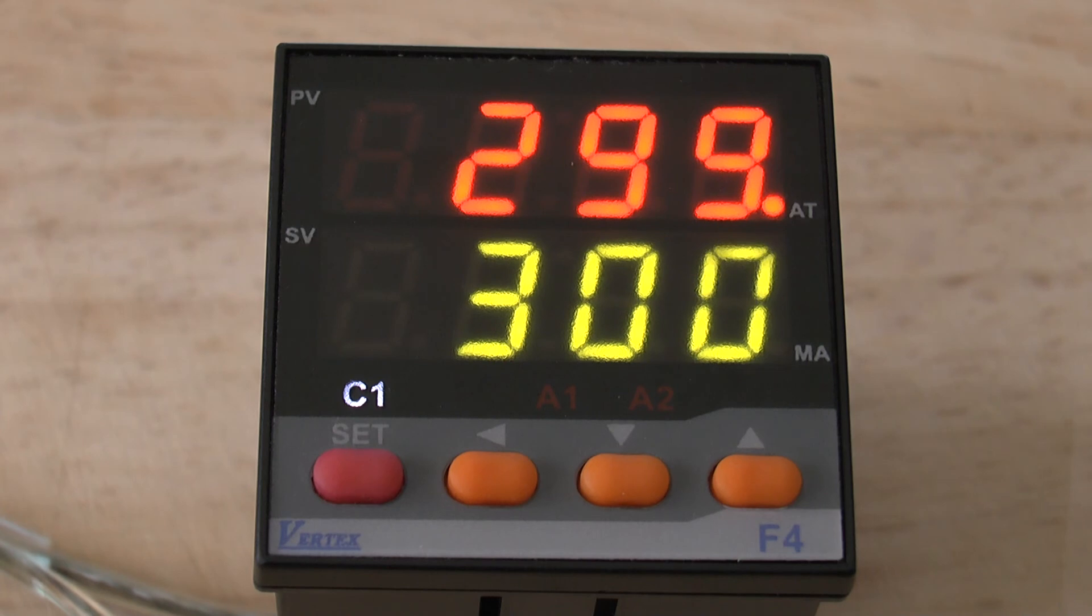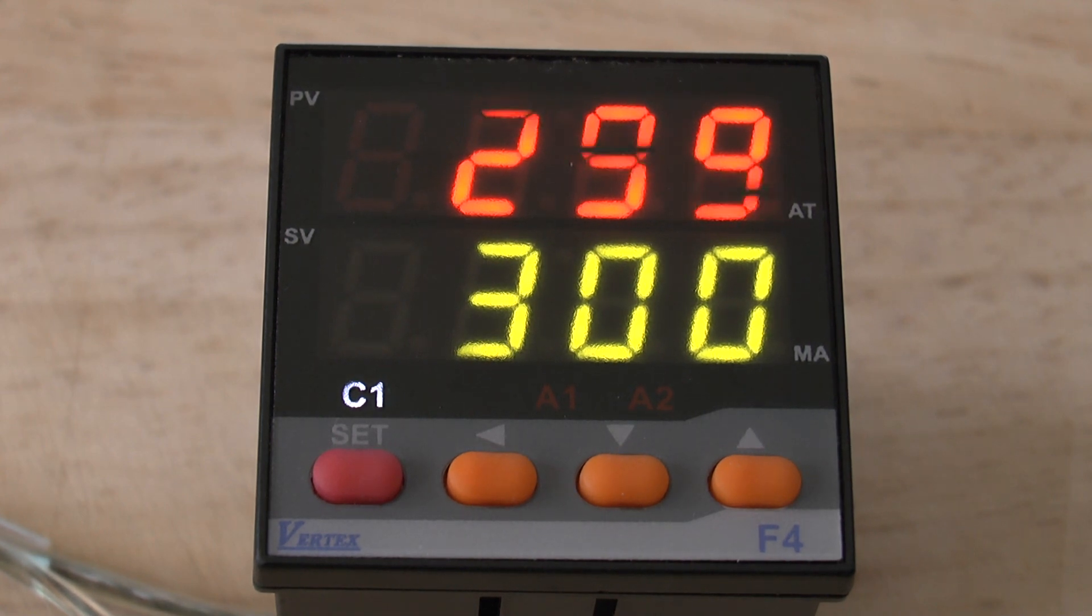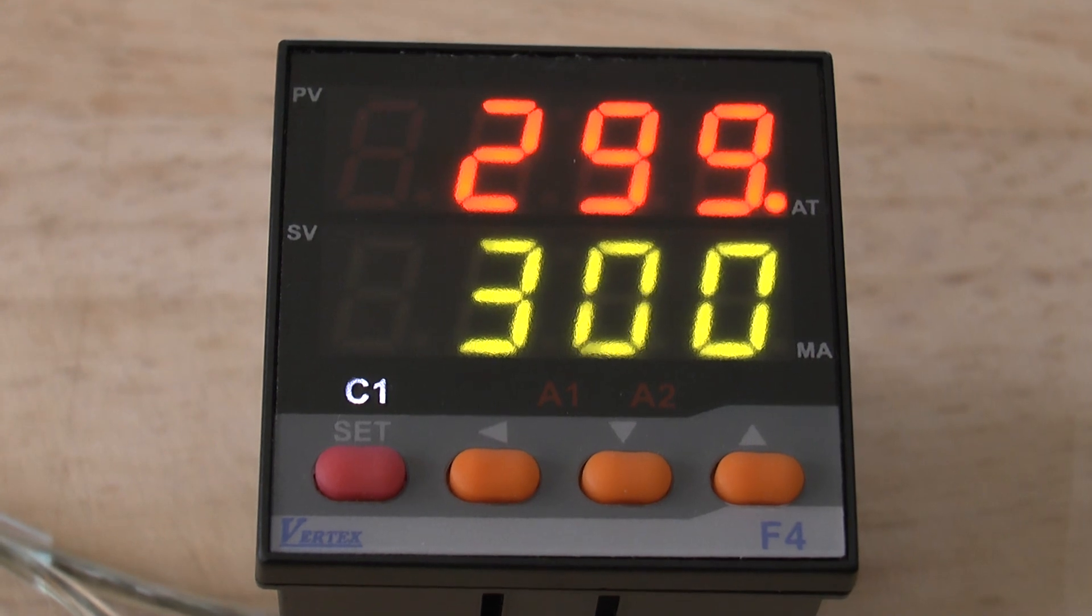It is important that while the controller is doing the auto-tune function, you do not change anything. For example, if this is on an oven, don't open the oven door or put anything else in the oven. Just leave it to do the whole auto-tune cycle, which could take a few minutes up to a maximum of 10 minutes, and then it will start controlling and give you good control at your SET point.